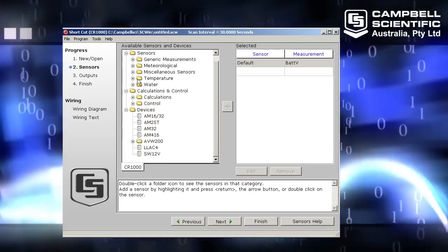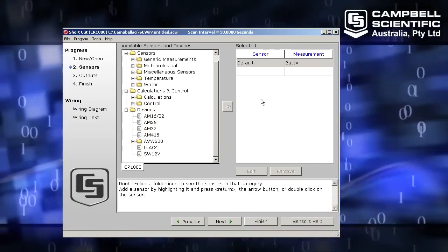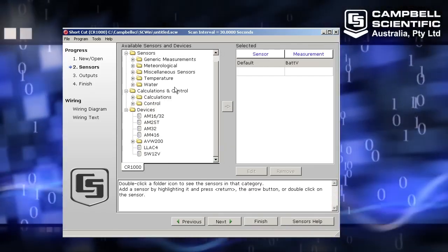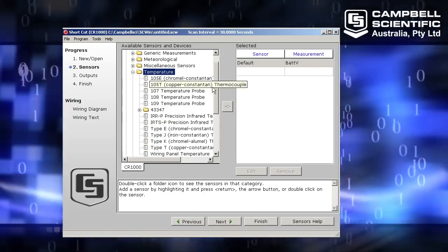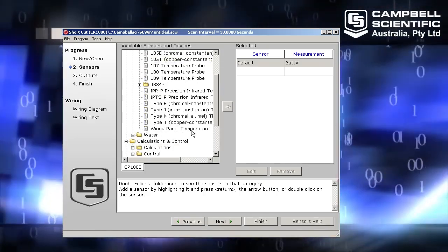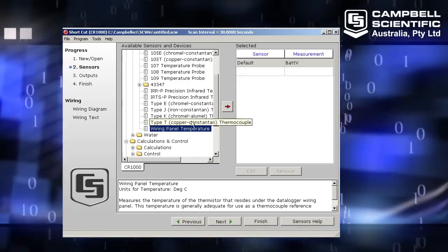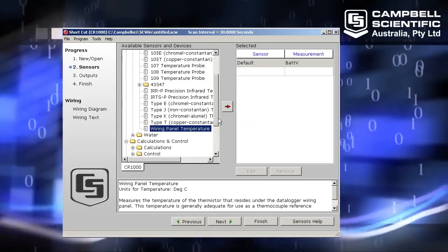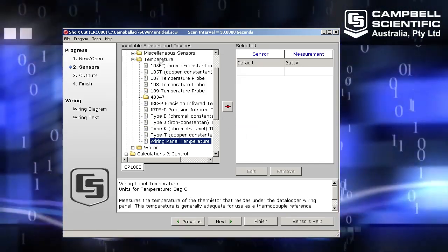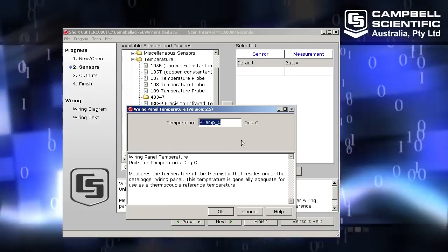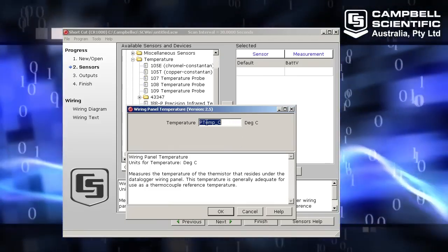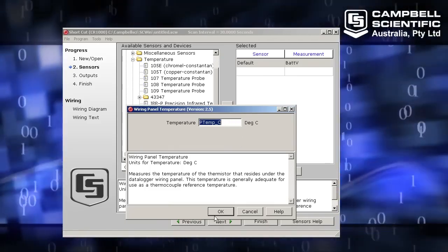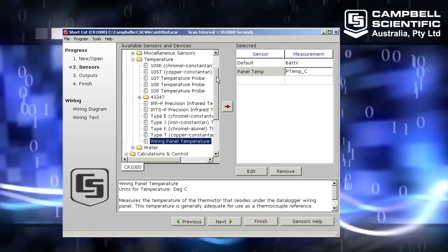Right, so here's my sensor selection screen. I'm going to be measuring thermocouples. So whenever we measure thermocouples we need to make sure that we are first measuring a wiring panel temperature. So I'm going to find wiring panel temperature under the temperature heading. I'll leave the default name. Okay, there we go.